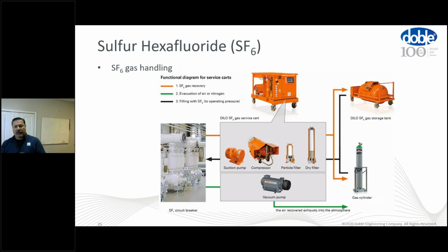So in gas recovery, very simple. We have our GIE on the far left. We've got our recovery system, which is made of a number of things, including a suction pump, sometimes known as a vacuum compressor, a compressor, onboard filters, particle filter and a dryer filter, and then our storage, which could be a tank or a cylinder or a number of cylinders. Our vacuum pump does not come into play at this point because we are doing either recovery or fill, depending on what you're doing. And if you follow the different lines, you see how that works.